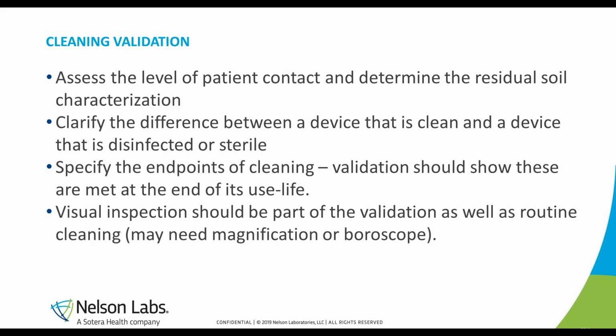For example, a device that has only incidental contact with the patient might require only spot cleaning, perhaps with a spray cleaner. Devices that have more contact with the patient's secretion may need to be fully immersed in a detergent bath or undergo ultrasonic soak or require manual brushing to clean. Other factors to be considered include the appropriate cleaning procedure and the justification of the acceptance criteria. These factors will form the basis for the cleaning validation, along with the validated parameters.